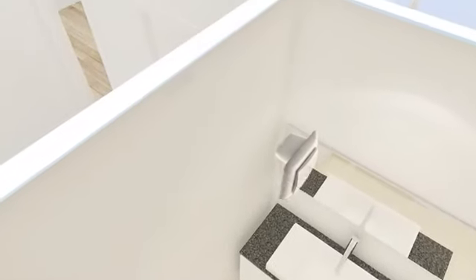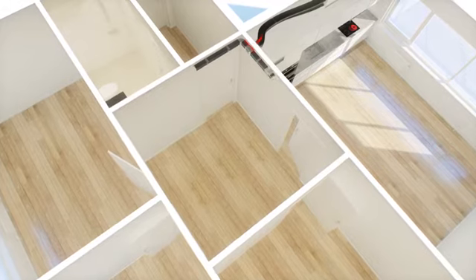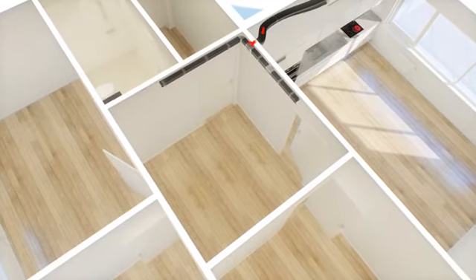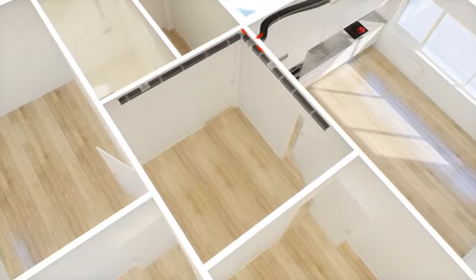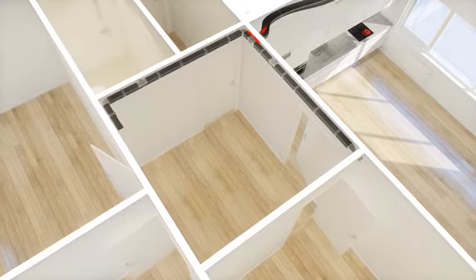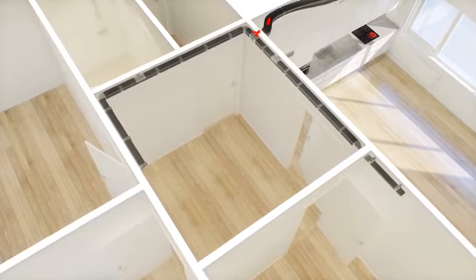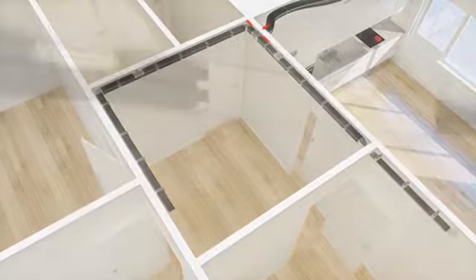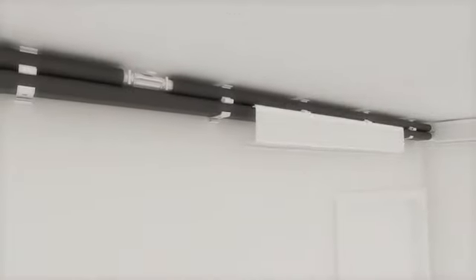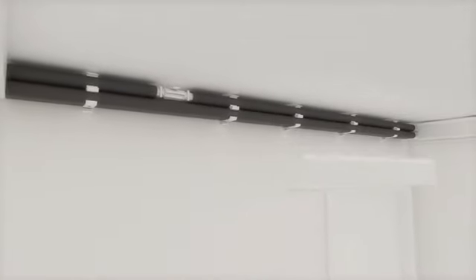The inlets for the extracted air are installed in the bathroom and in the kitchen. They are connected to the air handling unit via ducts located along the walls just below the ceiling. The duct for the fresh air supply ring is installed in the hall and connected to the air handling unit in the kitchen. Because of the special design of the ducts, the air can flow both ways in the supply ring, thereby greatly reducing the dimension of the ducts and the space needed for installing the system.